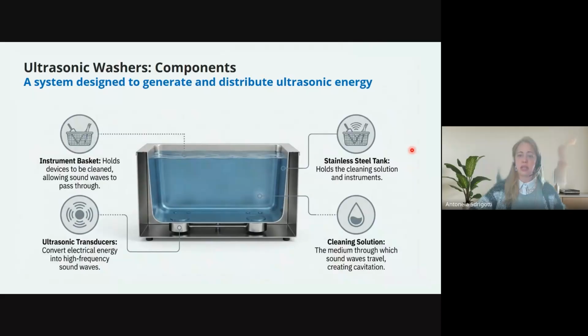The stainless steel tank holds the cleaning solution and the instruments, of course. And of course, that instrument will not be held directly in the tank. We have the basket that will hold the devices and instruments to be cleaned, which is a nest, a basket that will allow the sound waves to pass through the holes of the basket. So it's very important to consider the material of the basket so as not to reduce the cavitation energy that is reached by the instruments.